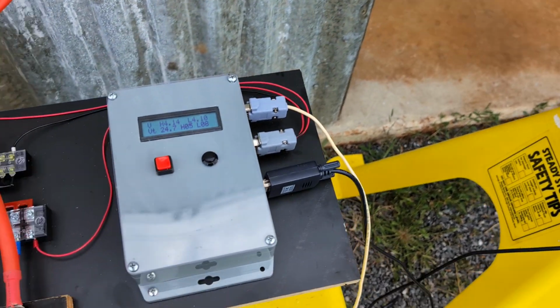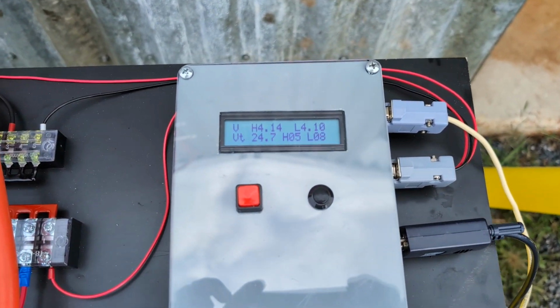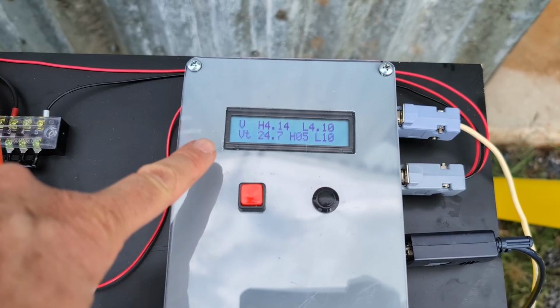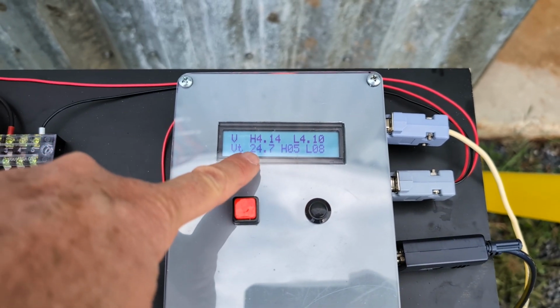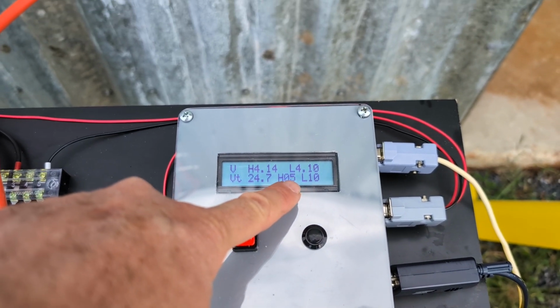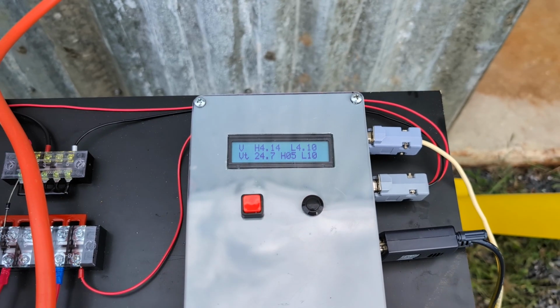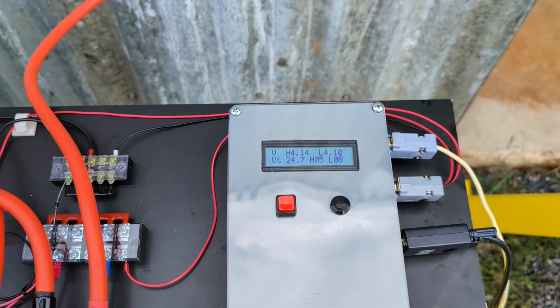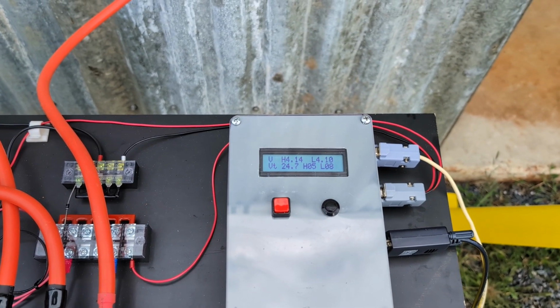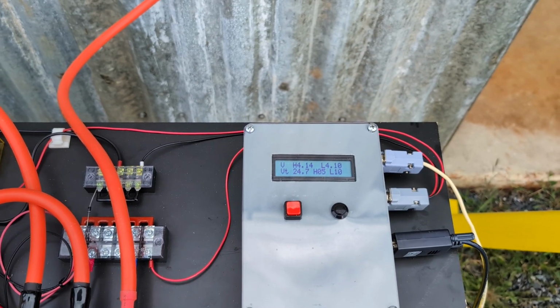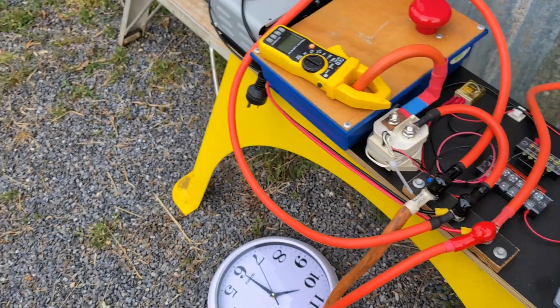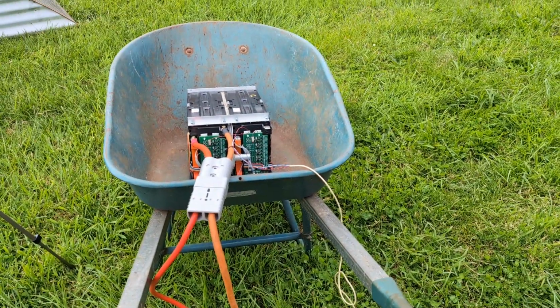So now I've got the other side connected. We're still monitoring all of the 12 cells, and so we can see now our highest is 4.14. We've gone down to 4.10 now because this discharge test discharged half of the cells for 30 seconds. I do want to keep the cells all very similar to each other, so I'm going to do the other side for exactly 30 seconds as well.